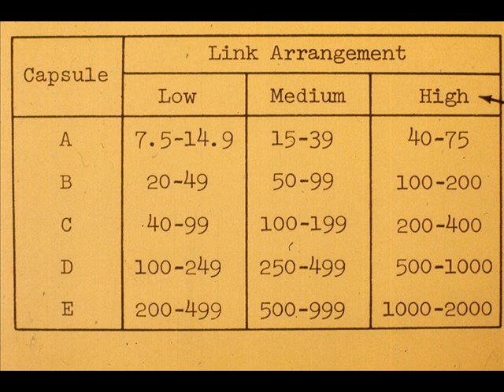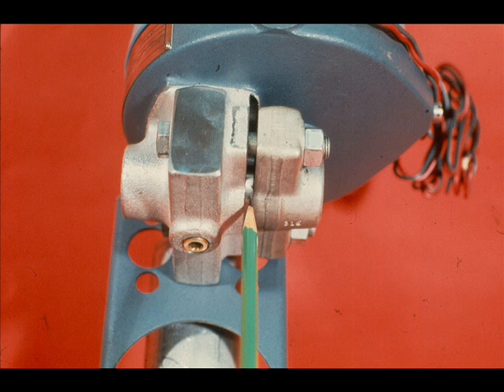This table designates the link selection for a given span for a particular capsule. This 0 to 50 PSIG transmitter contains a B capsule. We have a request to change the range to 0 to 200 PSIG.